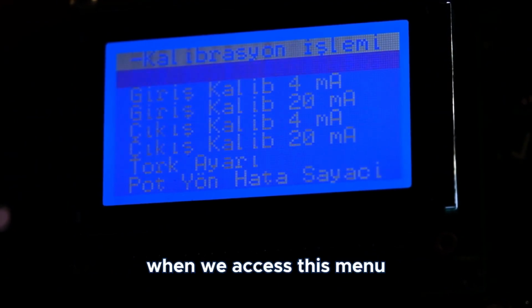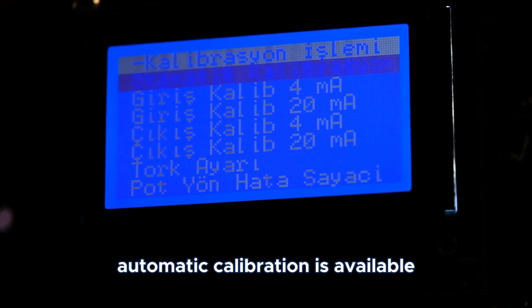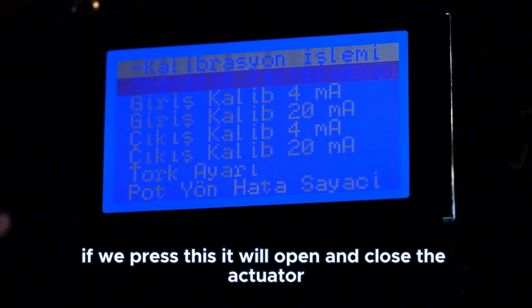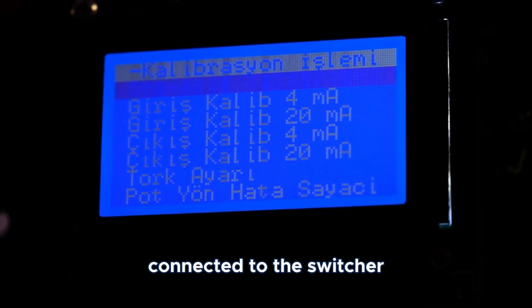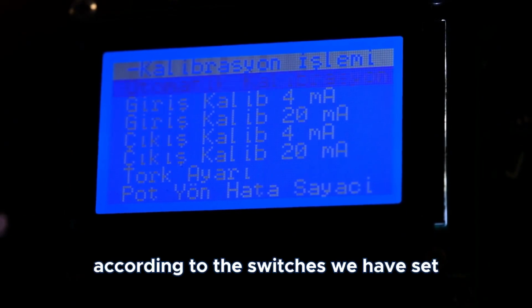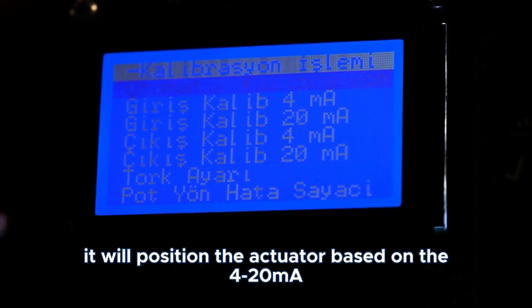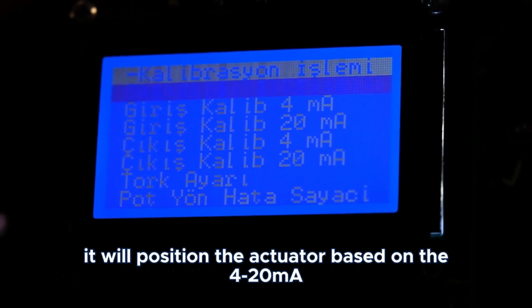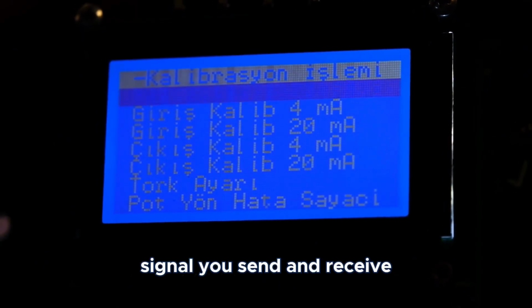When we access this menu, automatic calibration is available. If we press this, it will open and close the actuator connected to the switcher according to the switches we have set, and then it will position the actuator based on the 4-20 mA signal you send and receive.